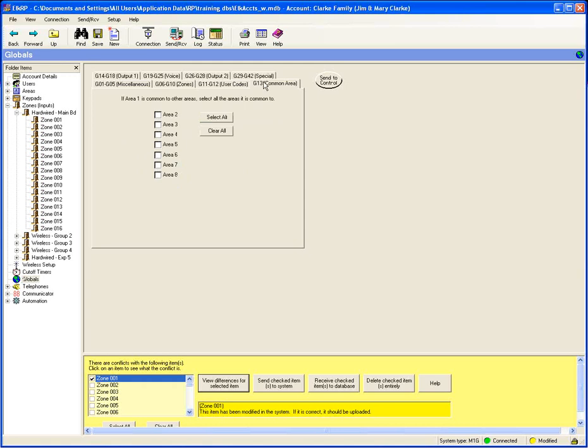I want to talk about common area. If you have areas common to Area 1, then Area 1 can't be armed until its common areas are armed, and if any of its common areas are disarmed, Area 1 will automatically be disarmed. This does not imply automatic arming of Area 1 — that can be achieved through rules. An example of when you'd use this: two different businesses in the same building, one as Area 2, another as Area 3, and Area 1 is the common lobby or vestibule they share.